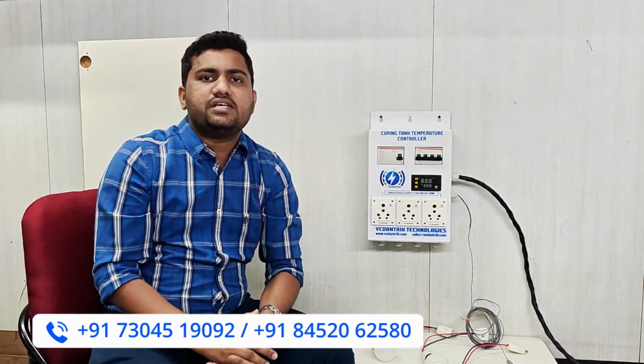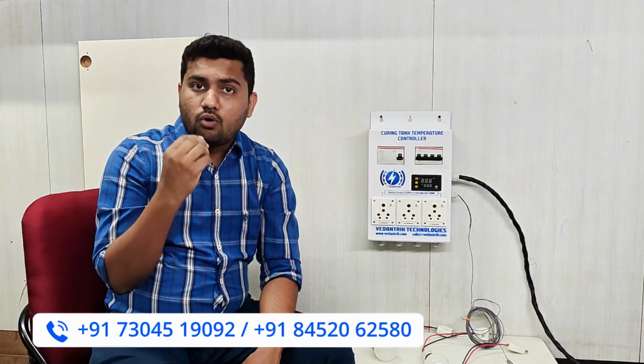Suppose, mostly if you see in laboratories or at sites, three-phase supplies are available. So always prefer to go with three-phase supply, because mostly the tank sizes are high, at least 2000 liter capacity. For a 2000 liter capacity, you will have to go for at least a 2 kilowatt heater. Whenever you connect a 2 kilowatt heater, that will draw around 8 to 10 amperes of current. 8 to 10 amperes of current is very high. So to minimize the value of the current, people go for the three-phase supply.